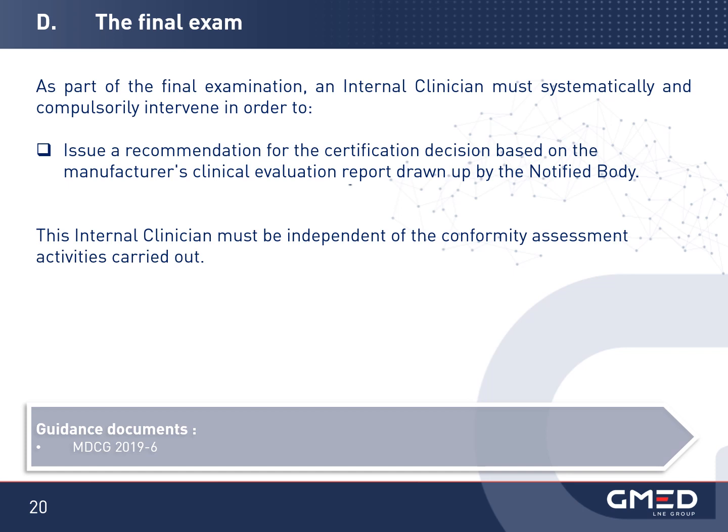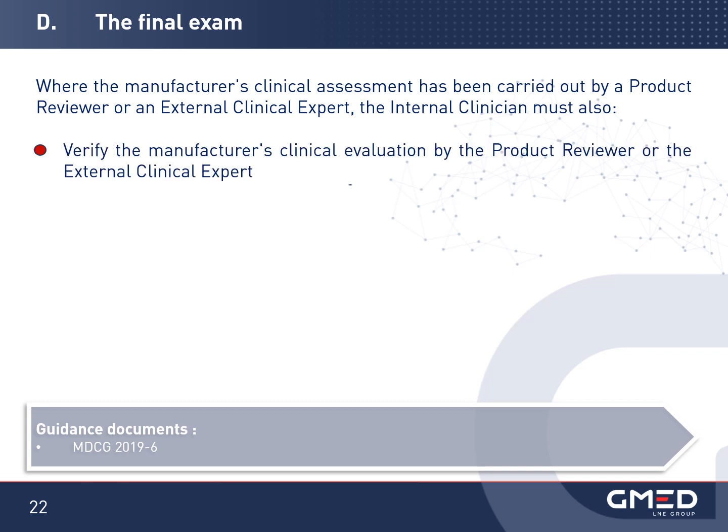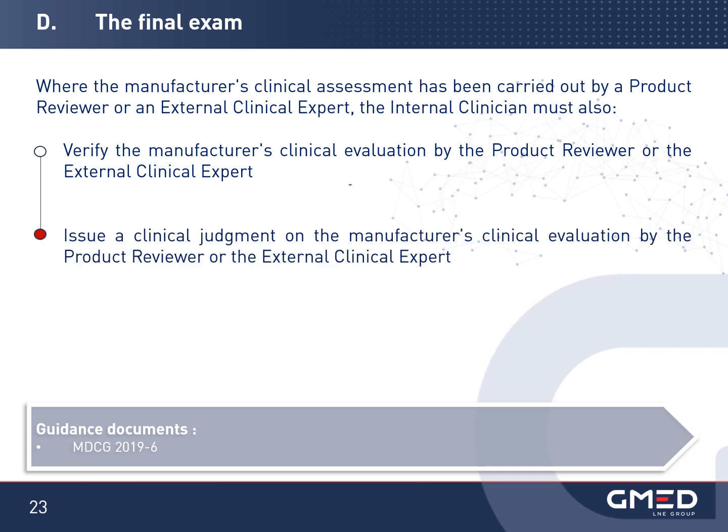The in-house clinician involved in this stage must be a medical doctor and also must be independent of the conformity assessment activities carried out. It is also important to note that when the manufacturer's clinical assessment has been carried out by an external product reviewer or clinical expert, the internal clinician involved in the final review must also verify the manufacturer's clinical evaluation by the product reviewer or external clinical expert, then issue a clinical judgment regarding the manufacturer's clinical evaluation carried out.